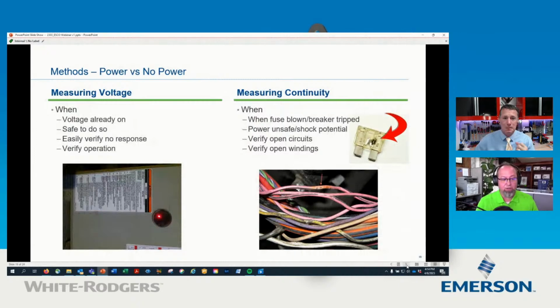Yeah. A couple other things of universal. Yep. Methods, power versus no power. When do you want to use voltage? Well, when your voltage is already on, it's safe, and you can verify that you're not getting response out of something. In other words, your igniter's glowing or your sparker is sparking, and you should have gas coming on. And by standing over to the side, you can put your leads on your gas valve, and you should get your 24 volts on it when that gas valve circuit should be energized.